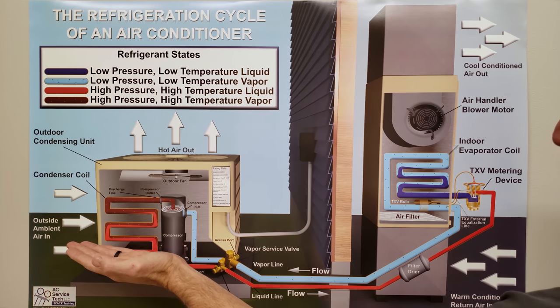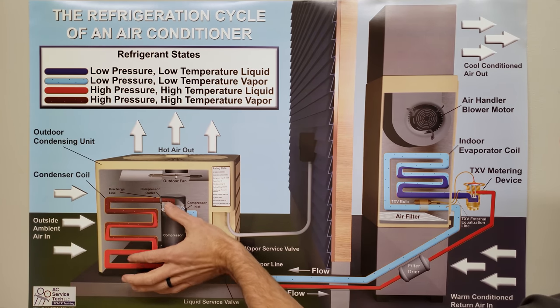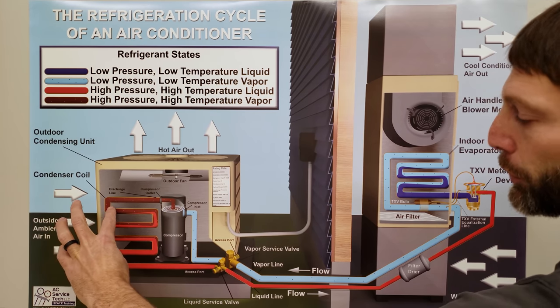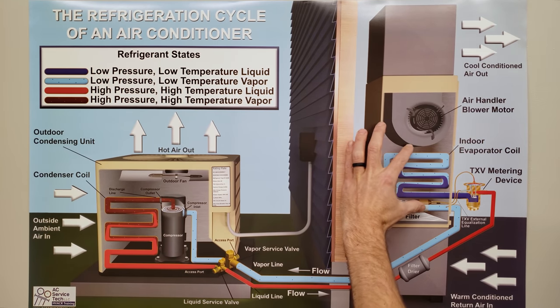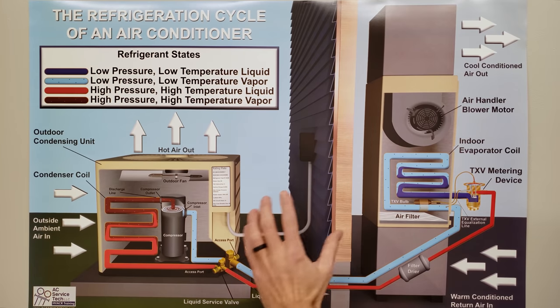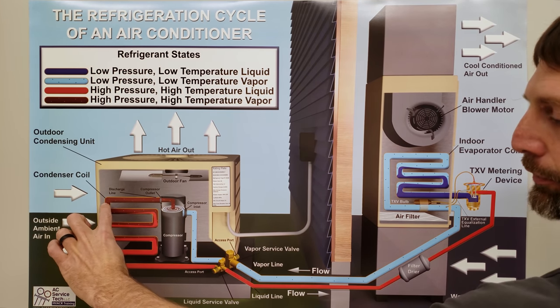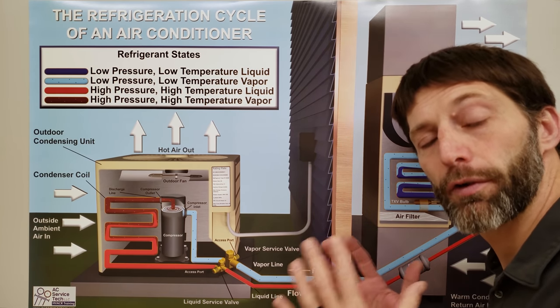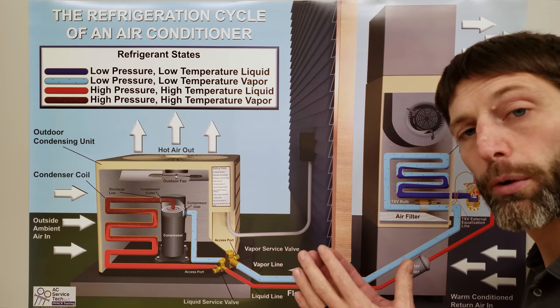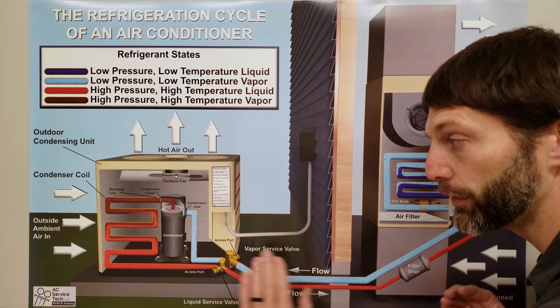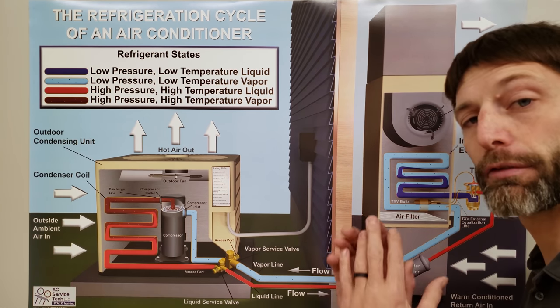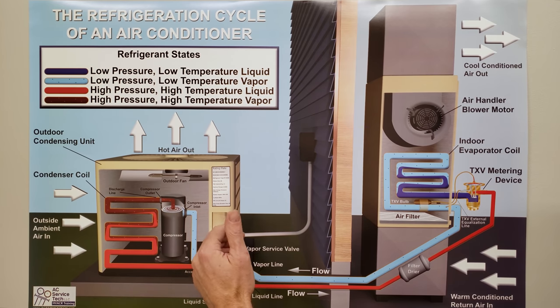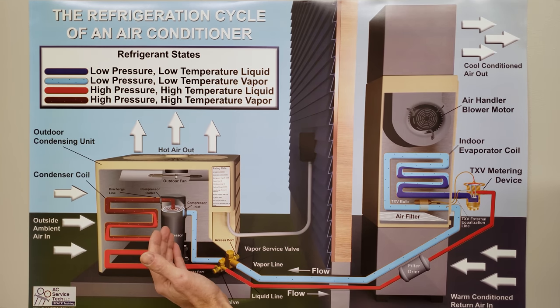When you see liquid and vapor both in the coil at the same time — this represents the outdoor coil and this represents the indoor coil — that saturated refrigerant is the key, the secret to the refrigerant's ability to absorb heat here, move it to the outside, and reject it there.